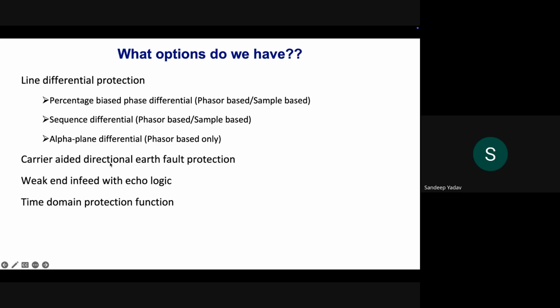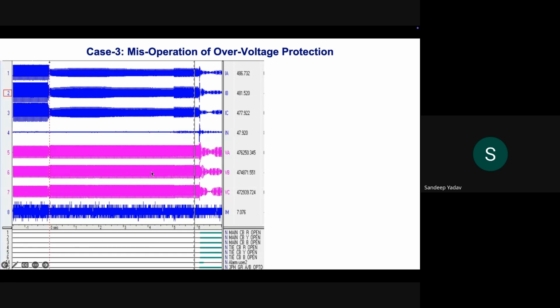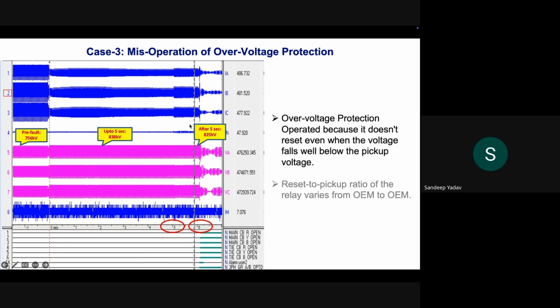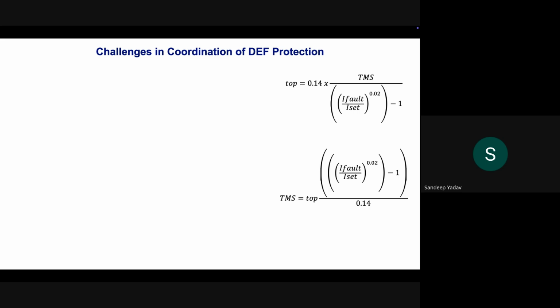There are other makeshift arrangements in the protection which can be used. So we can use carrier aided directional fault protection, weak end infeed logic can be used, and time domain protections, they can also be used. Misoperation of over voltage protection, we just saw a few slides back that because of the low pickup to drop off ratio, which was 98%, the over voltage element picks up, but it does not drop off in time. As a result, the maloperation or the misoperation of over voltage protection takes place. So this was changed.